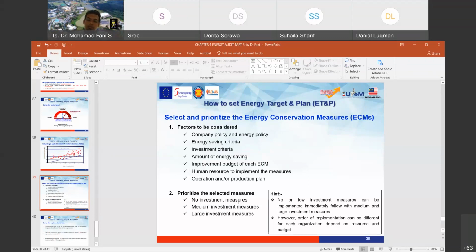When we did the walkthrough energy audit, we found that these 4 cooling towers were a kind of loss, because the OEM, the manufacturer, maps 1 chiller to 1 cooling tower. So they were running 4 cooling towers, and 2 cooling towers contribute to more energy use.